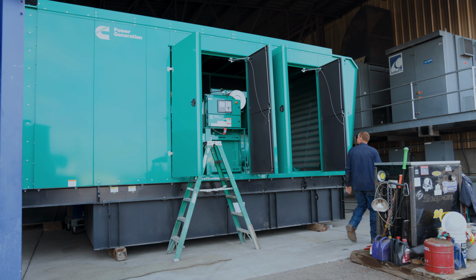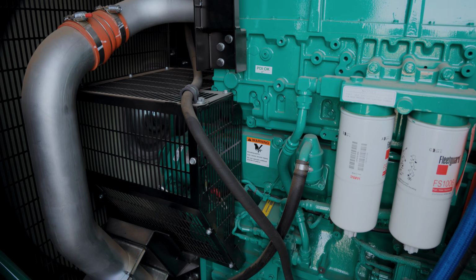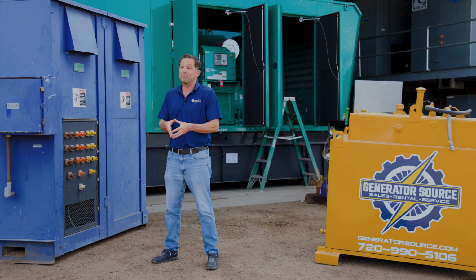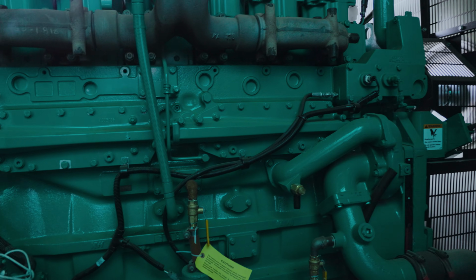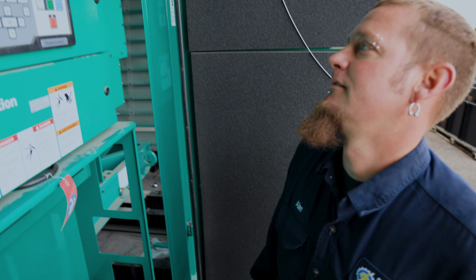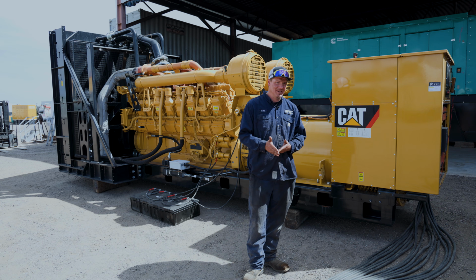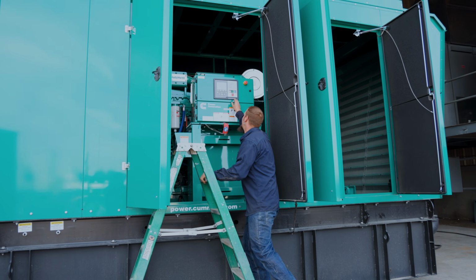Sometimes the customer will say, well, we don't need to do this because the unit just sits all the time. The more the engine sits, the more the fluid sits, things can break down, and it's actually not good for the engine. So we want to run it at full rated capacity to make sure that it can perform in the event of an outage.